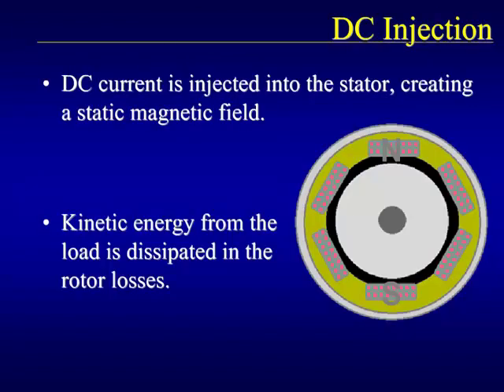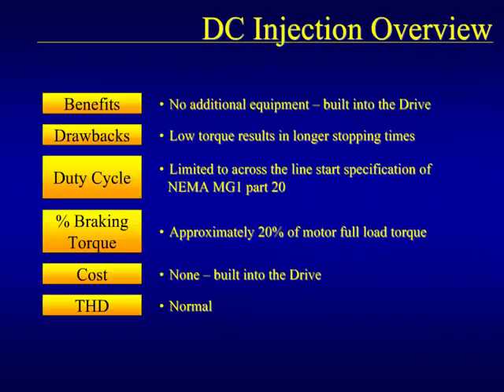The simplest form of braking is DC injection. DC injection works by sending DC current into two phases of the motor. This DC current causes a static magnetic field to occur, which attempts to lock the rotor in a fixed position. During the braking process, all of the kinetic energy from the load is transferred into rotor losses, most notably heat in the rotor. One of the greatest benefits of DC injection is that the function is built into the drive — no additional components are required, preventing any additional cost when using this braking method.